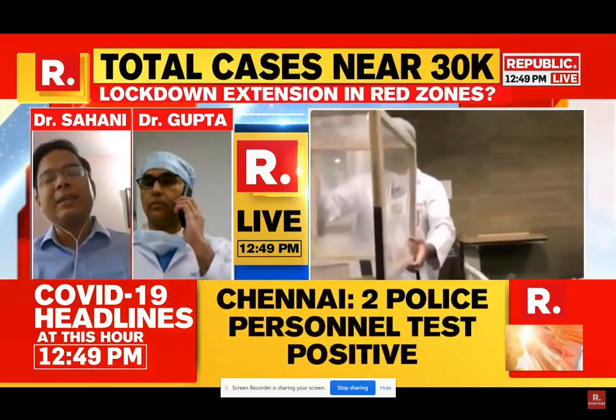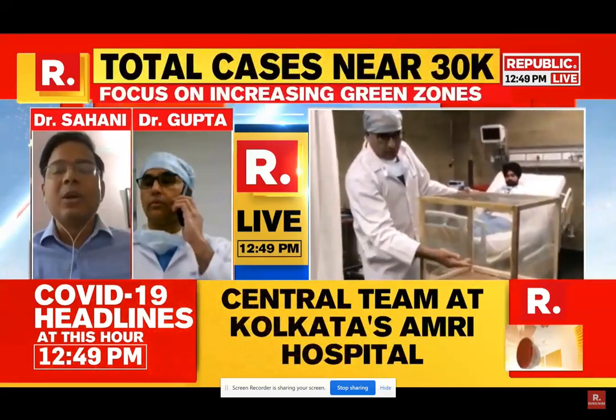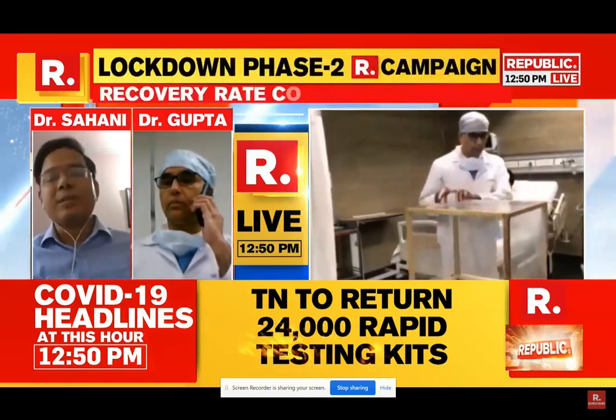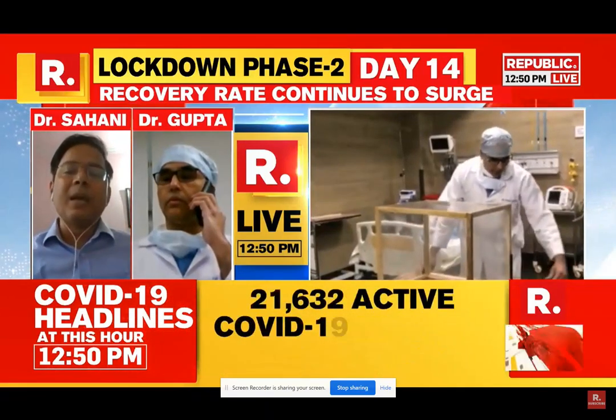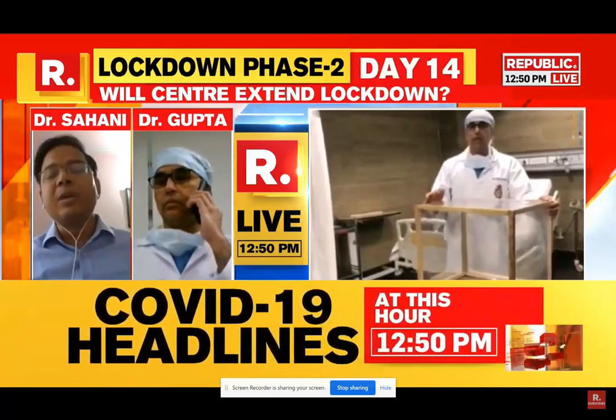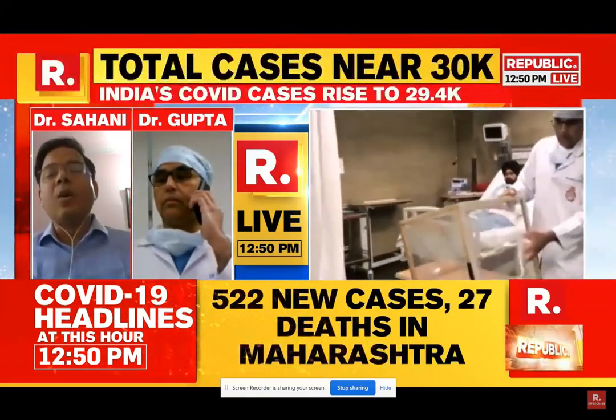Because the current supply chain is broken and most hospitals cannot get what they want, we have designed this so that hospitals can make it themselves very easily with available manpower and resources. It costs within 500 rupees to make. Most COVID patients are supposed to be in negative pressure rooms, but most hospitals don't have many — and building them is very expensive — so this box can simply contain the viral load of the patient.